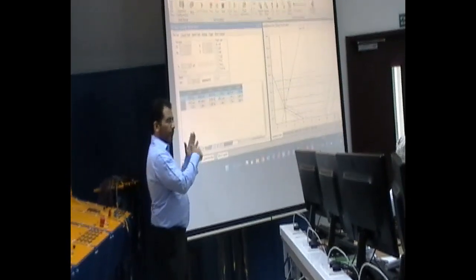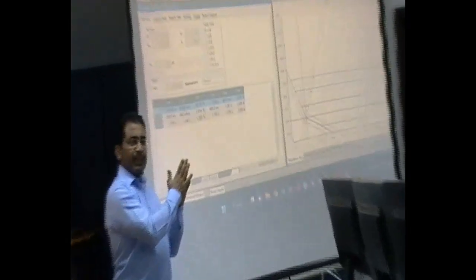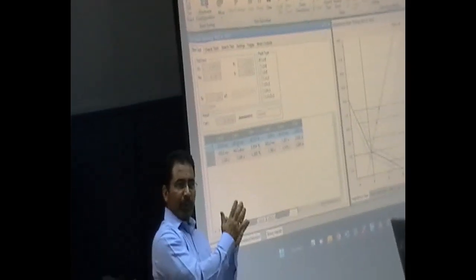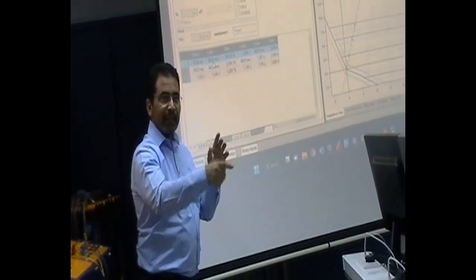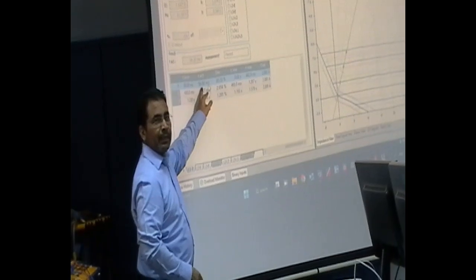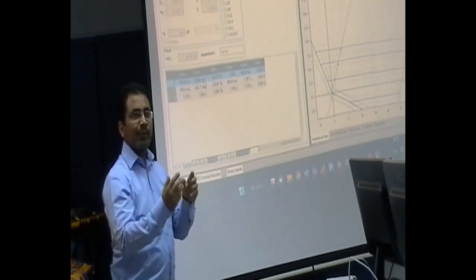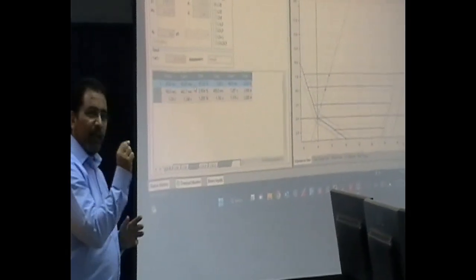Muhammad, the algorithm here is FFT. It takes a full cycle for measurement of the amplitude of the signal, taking the Fourier transform, and after 40 milliseconds, it will decide. So this is why we have 58 milliseconds. It takes 2 cycles to decide if it's a fault or not, and then send the signal. The signal also takes time through the output contact of the relay.